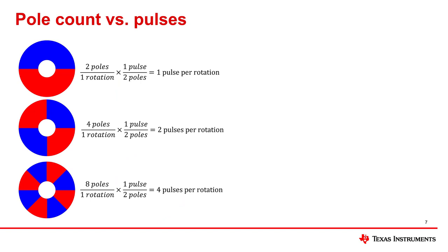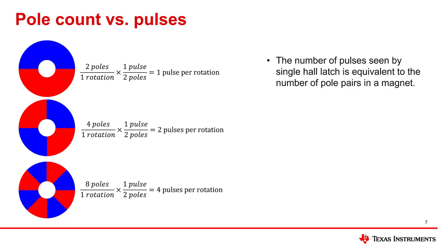As mentioned previously, with more poles there are more transitions. The amount of pulses seen is determined by the amount of pole pairs present in our ring magnet. If we use four poles — two north and two south — then we will see two output transitions throughout the impeller's 360 degree rotation.